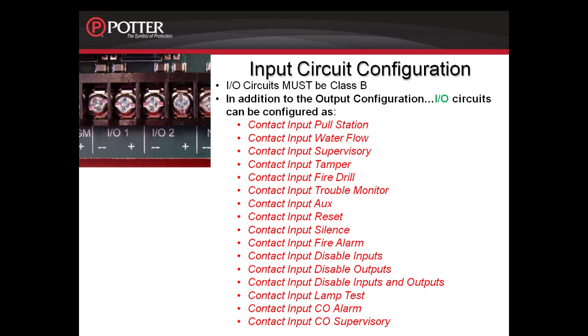This list is found in the software, and each circuit can be configured individually as to what you want to monitor. For example, if I want to monitor a conventional duct detector for a supervisory condition, I can set up the I/O circuit to be contact input supervisory. If I wanted to monitor a CO detector with one of the I/O circuits and I wanted that to be an alarm condition, I would set up the I/O circuit as contact input CO alarm.